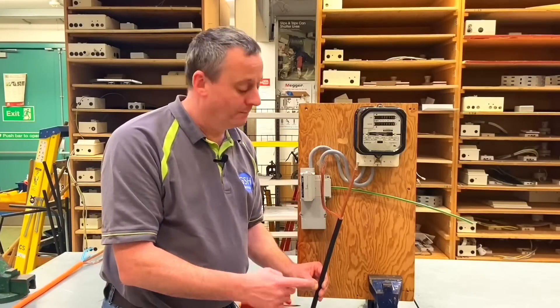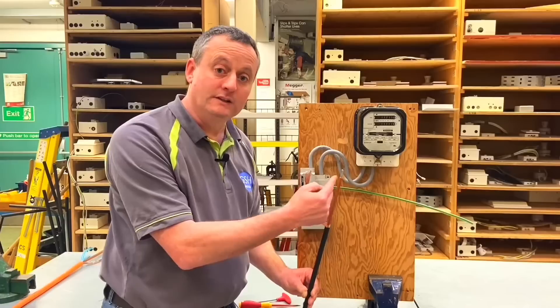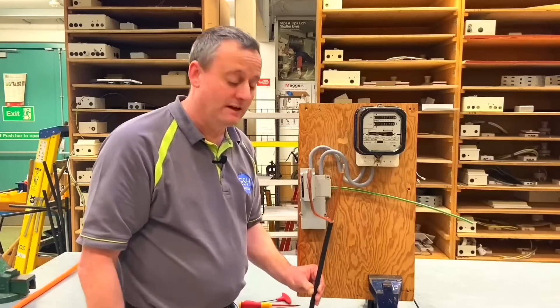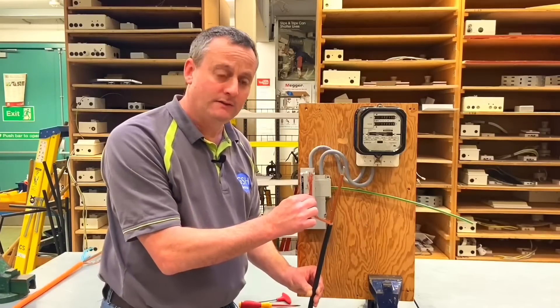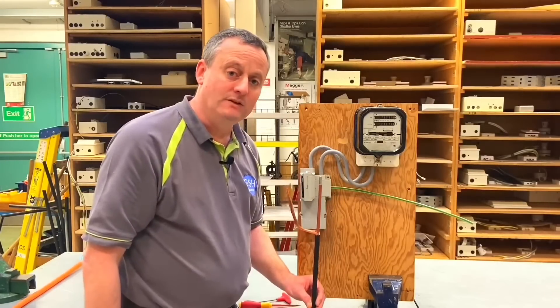This is a concentric cable - not steel wire armoured. It looks like a steel armoured cable until you strip it back. It has a combined neutral and earth, and a line conductor - in this case aluminium for the line conductor and copper for the neutral and earth. Let's have a look inside and see how that's going to be connected.